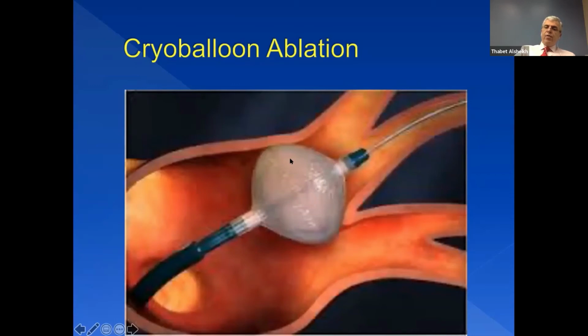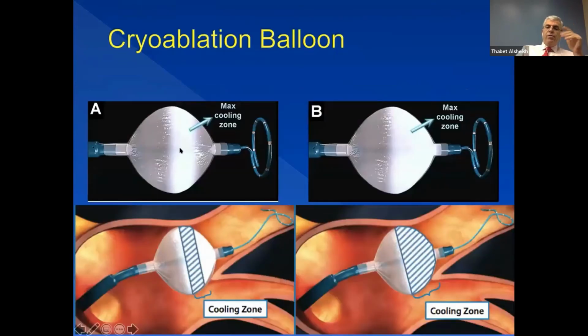So we put the balloon in, we inflated contact points, then we run nitrous oxide as it goes from liquid to gas phase. It freezes and drops the temperature as low as -80 degrees Celsius. Once the tissue temperature drops below -40, you really create irreversible damage and you create a scar. Earlier balloons had that freezing or cooling zone limited to only part of this half sphere. And only the contact points, of course, can cause the damage. In this area here, you're not in contact with the tissue, so you don't have damage to the tissue. So you can still have a gap here that needs to be frozen or create a scar for it.